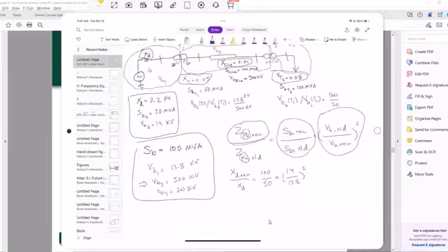All right. So we chose the new base values: S base equal to 100 MVA, V base 1 equal to 13.8, V base 2 equal to 500 kilovolts, V base 3 equal to 20 kilovolts. This was what we did. Now, using this formulation, XT new over XT old would be the same as S base new over S base old. But what is S base new? S base new is the new base of the system, the common base, which we chose to be 100, right? And what is S base old? S base old is the one on the nameplate of my generator, which is 50. So here is 100 over 50.